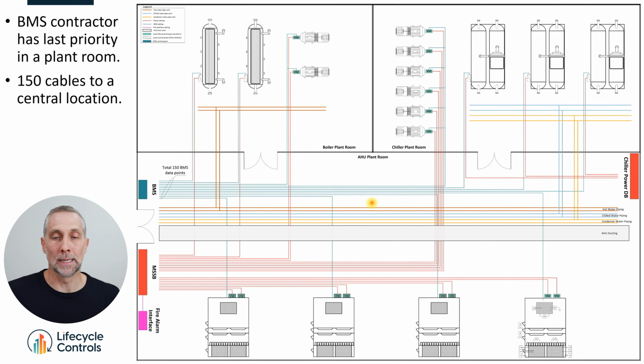Now, in previous years, what used to happen is when the mechanical electrical was finished, the BMS installer would have 2 or 3 weeks to finish off the installation, get all their cables down these common congested areas back to our centralized, and centralized is an important word, our centralized control panel. Problem nowadays with all the pressure on construction and to get jobs done, usually what happens is when the very last power feed is connected to the variable speed drive, mechanical wants to power up these boards and start air and water balancing because they're a month late. So what happens is the BMS installer is under extreme pressure to get their cables in because there's just no time to even do the BMS installation properly.